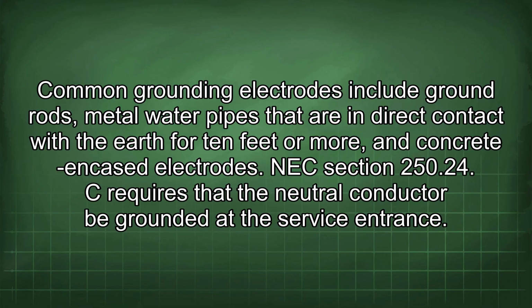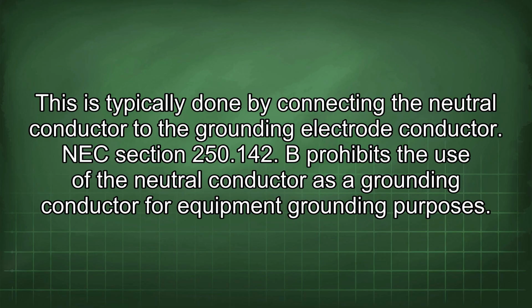NEC Section 250.24(C) requires that the neutral conductor be grounded at the service entrance. This is typically done by connecting the neutral conductor to the grounding electrode conductor.